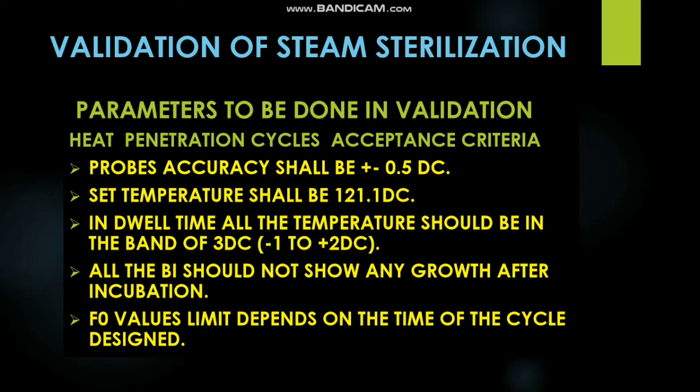All the BIs should not show any growth after incubation, and F0 value limits depend on the cycle design. Whatever F0 value is required to be achieved as per the cycle design, it should be above the limit. So if a 20-minute cycle is there, then your F0 value should be more than 20. If a 30-minute cycle is there, then it should be more than 30.